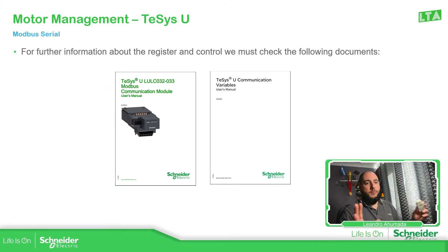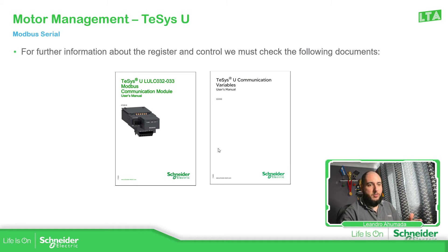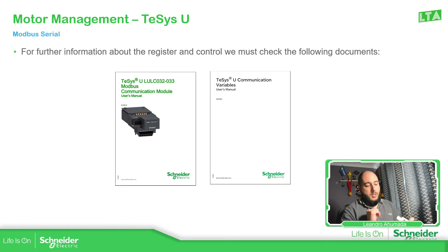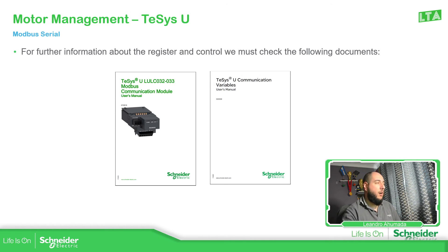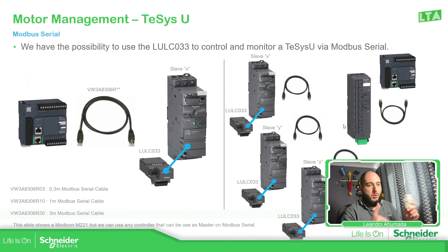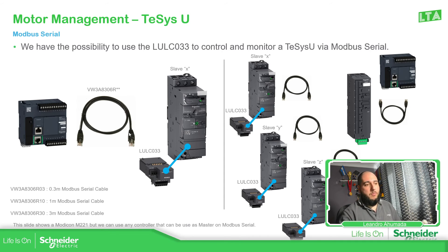The key reference here is the communication manual document, which gives you the same information I've presented: how to configure the unit using the switches on the back, how to assign the communication settings, and the voltage on the terminals, as well as identification of the LEDs. You also have multiple architectures available, but the basic one is what I've shown. For a point-to-point connection, you should check the terminal resistor. If you have more devices, you can add them using this Schneider cable, depending on distance and other factors.